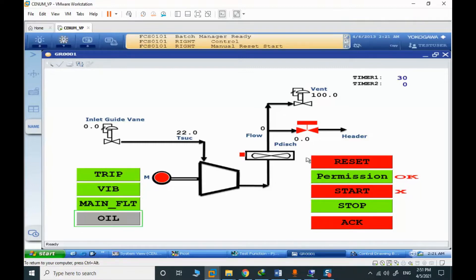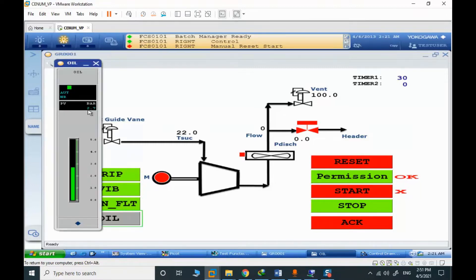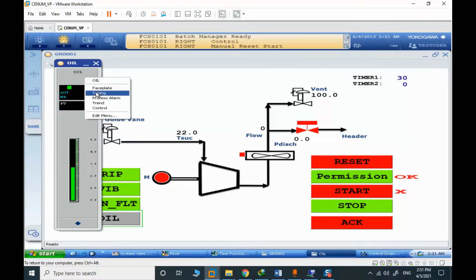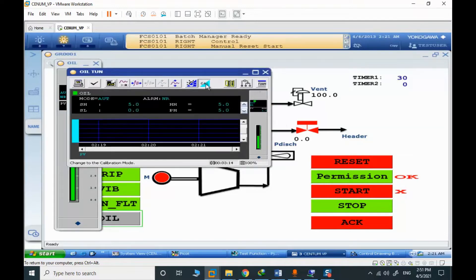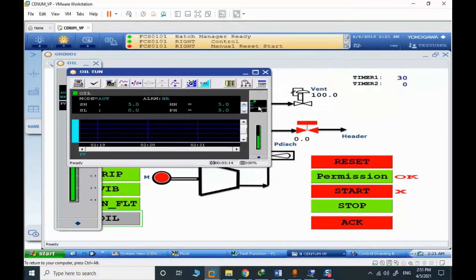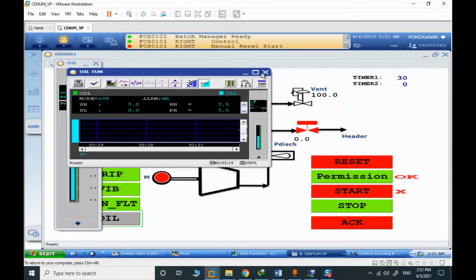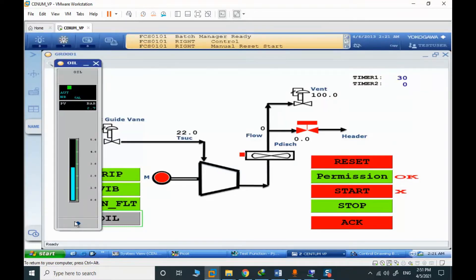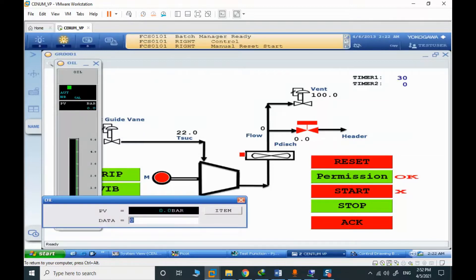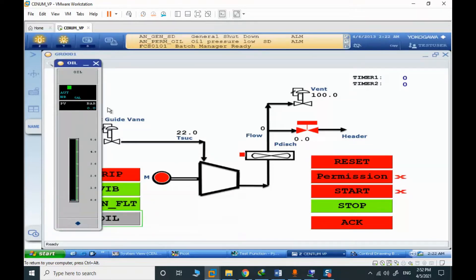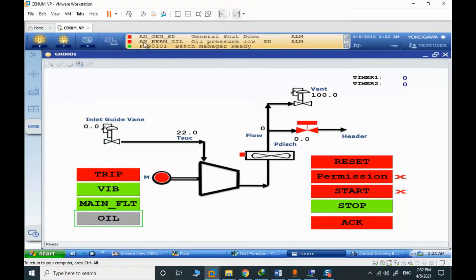We have the correct pressure here. It's possible to change and modify the oil pressure in calibration mode. You can change the value and see when I change the oil pressure to zero, the permission will shut down. And we have the alarm here that oil pressure is getting low.